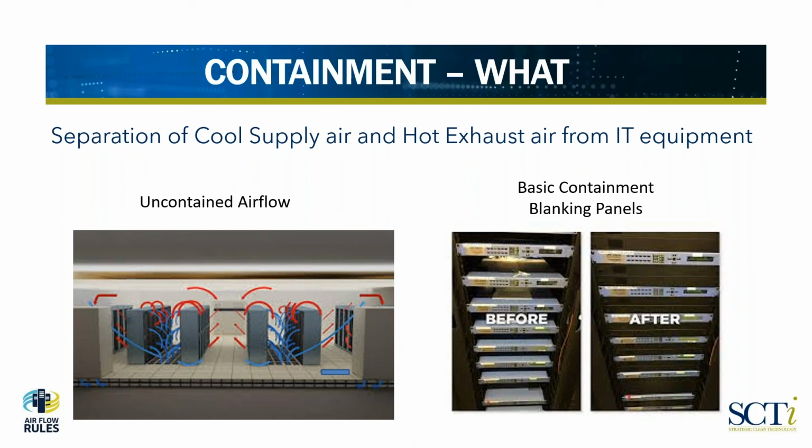Yeah, very true. You bring to mind a site that we were in recently where when we go into a site and do the audit, part of what we do is measuring the airflow coming out of the perforated tiles relative to the amount of airflow that's being provided by the cooling units. And it's not unusual to do our measurements, and when we do the calculations and tally it up, we find that there's 65% less air coming up through the perforated tiles than what's being provided by the cooling units. So that's, to your point, Carrie, that means that there's a lot of air coming up through the floor and other places rather than perforated tiles.